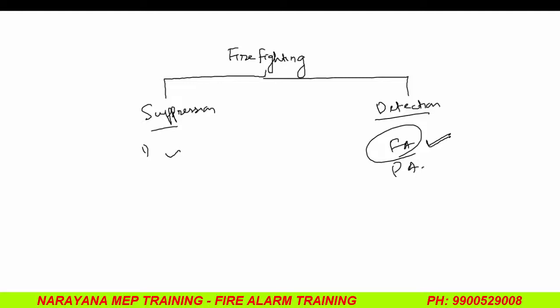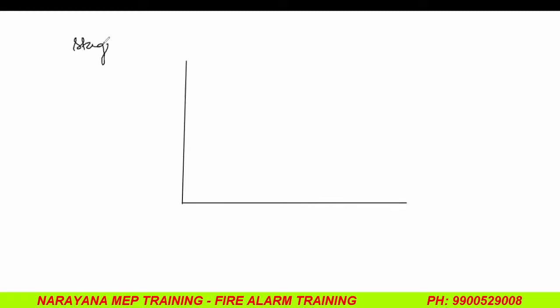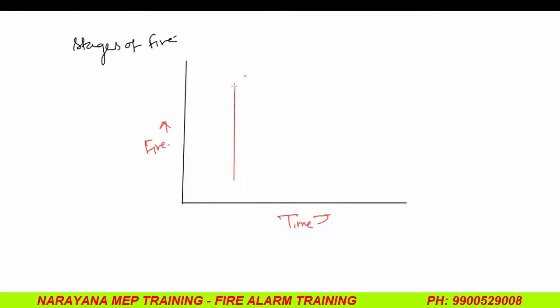If I draw, this is the stage of fire — different stages of fire. On this side is fire intensity, and this side is time. There are basically four stages of fire. In the first stage, nothing is visible, but we can still get an alarm. That is called the air sampling method, or VESDA — Very Early Smoke Detection Apparatus.